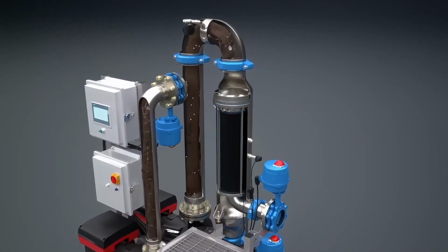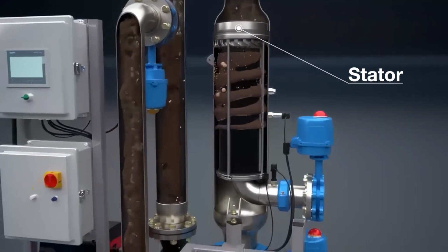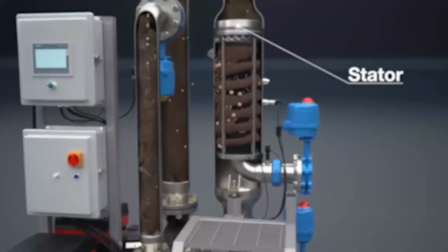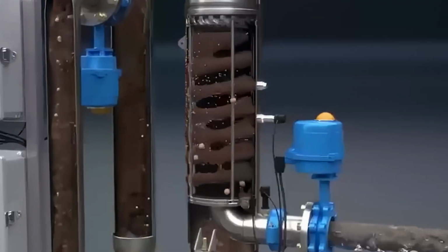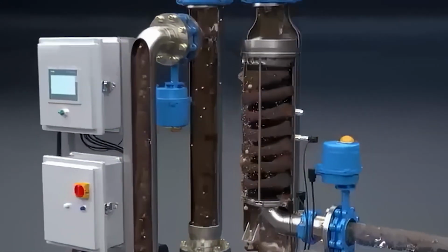The combined stream enters the top of the housing and flows through the stator, which directs the fluid downward into a helical motion. The motion turns the rotor that is connected to the brushes. This results in an active brush cleaning process.